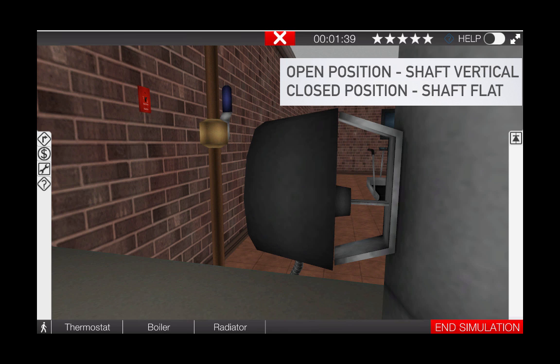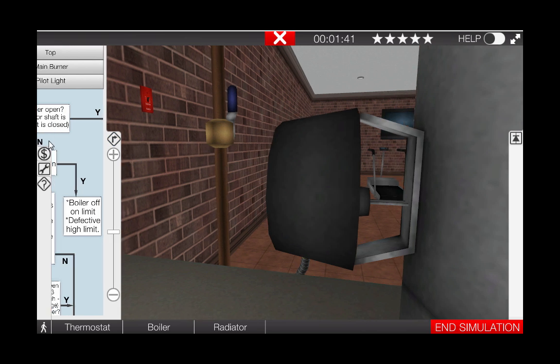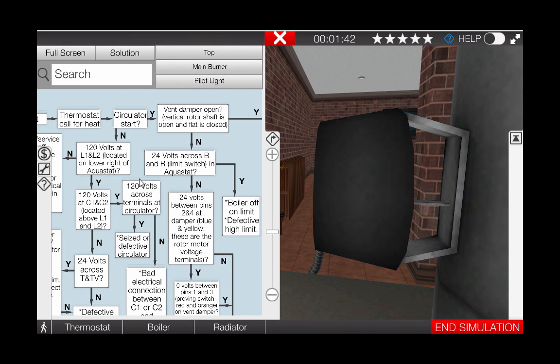With the circulator operational and the vent damper not opening, we've narrowed the problem down to either the combination Aquastat, which sends power to the vent damper on a call for heat, or possibly the vent damper itself is the fault. Let's find out.